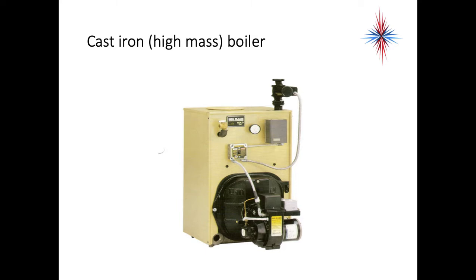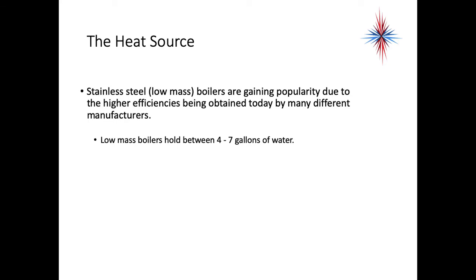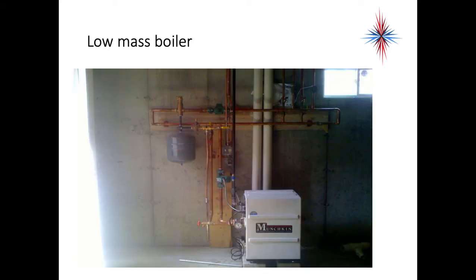From a cold start, it takes a lot of fuel to heat that water to a temperature where it will actually heat the space. Low-mass boilers, like stainless steel boilers, are gaining popularity due to higher efficiencies. Low-mass boilers only hold between 4 to 7 gallons of water. This is an example — a little Munchkin boiler sitting on the ground. It's high efficiency, which you can tell by the PVC vent pipes. Some are now designed to hang on the wall as well.